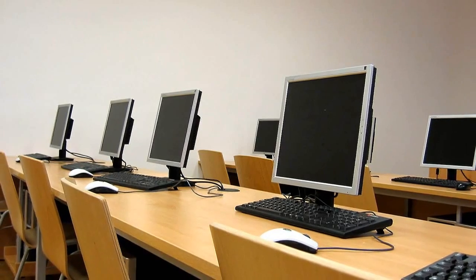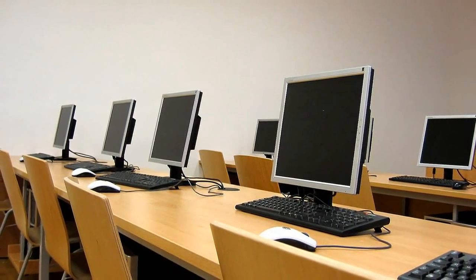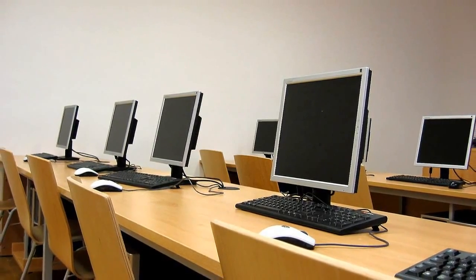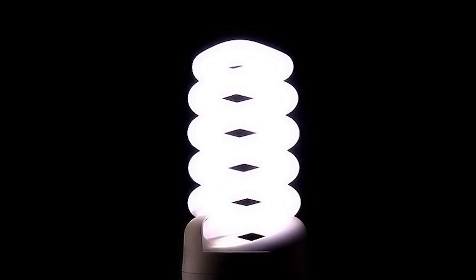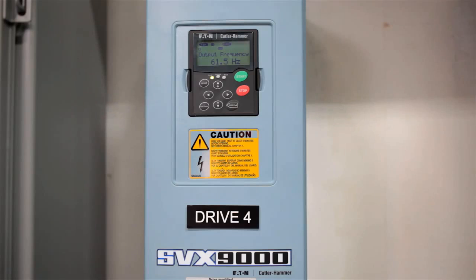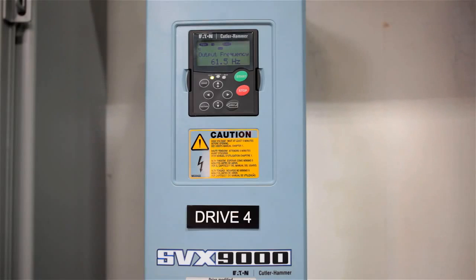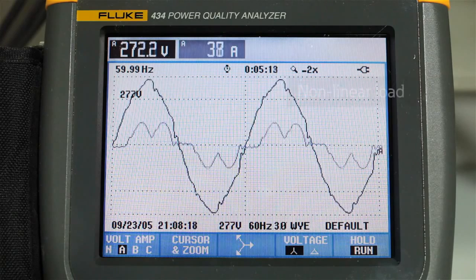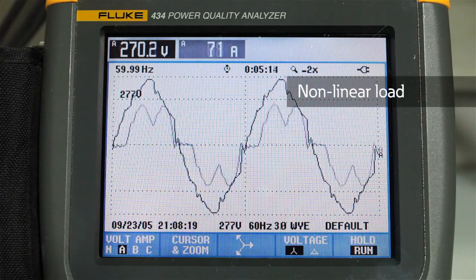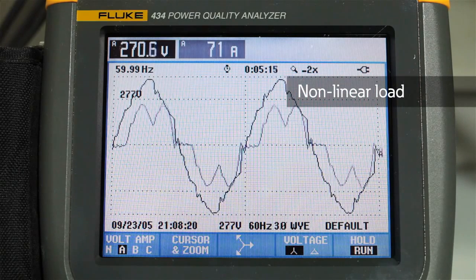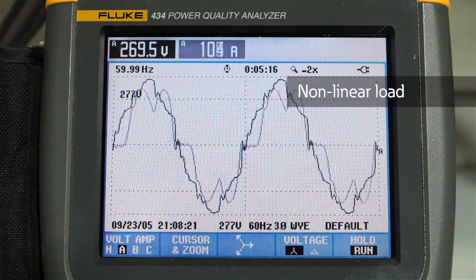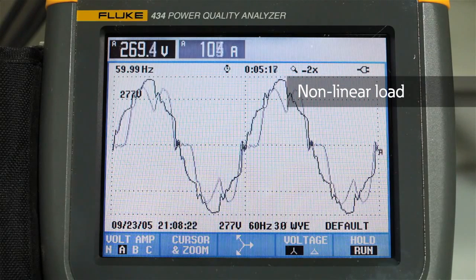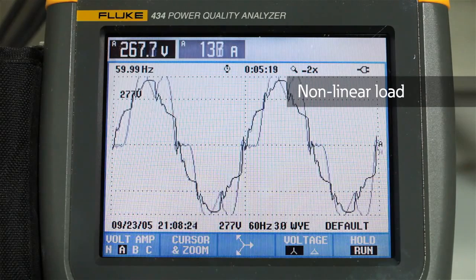Non-linear loads such as computers with switch mode power supplies, fluorescent lights, and variable frequency drives draw current that does not look similar to the voltage. This non-60 Hz current distorts the waveforms of the entire distribution system.